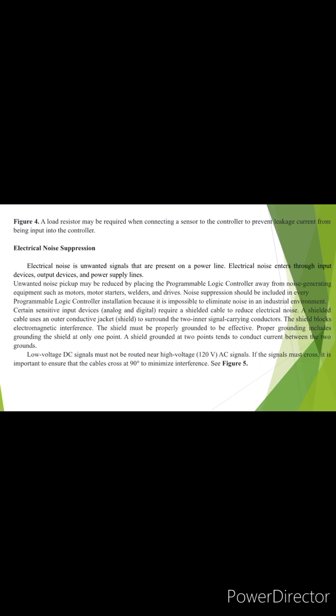Electrical noise suppression. Electrical noise is unwanted signals that are present on a power line. Electrical noise enters through input devices, output devices, and power supply lines. Unwanted noise pickup may be reduced by placing the programmable logic control away from noise-generating equipment such as motors, motor starters, welders, and drives. Noise suppression should be included in every programmable logic control installation because it is impossible to eliminate noise in an industrial environment.